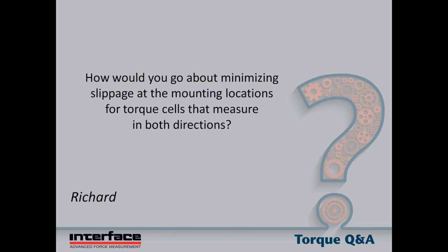Usually you can tell if there's slippage if you, say in calibration at least, look at the shape of the calibration curve, and if there's slippage, instead of a smooth curve, you get some irregularities and discontinuities as the torque is applied. In many cases, certain torque sensors on the market actually don't have enough clamping force, even if appropriate hardware is used. And that tends to be in the case where you have multiple capacities in the same package size. In that case, if you're going to have reciprocating torques, and say especially in a fatigue application or an application where you expect that there'll be a lot of changing direction, it's important to address that, and that can be addressed by either having a sensor that has more mounting holes at the same capacity, or on a bigger bolt circle, bigger bolt holes, or all of the above.